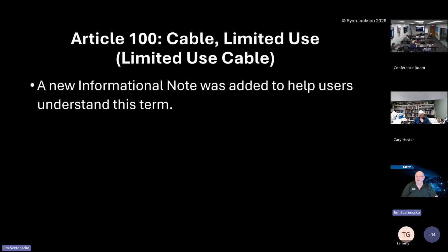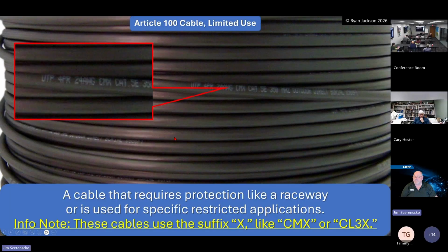Cable, limited use, also a new informative thing on the wiring. You're going to see that these cables use the suffix X, like CMX or CL3X. A cable that requires protection like a raceway or is used for specific restricted applications. So if you see this limited use cable, it's either got to be installed in a raceway or it has to be installed in a certain place or in a certain way.